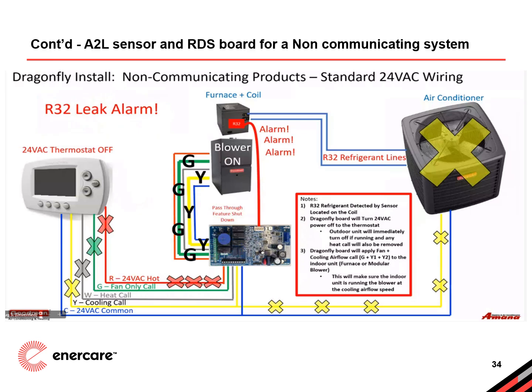At the same time, the RDS controller forces the indoor blower to run at cooling speed. This is a crucial step because it helps ventilate the area and dilute any refrigerant concentration. The benefit to this setup is that the RDS board usually just acts as a pass-through for signals between the thermostat and the system. But when something goes wrong, it overrides everything to prioritize safety, even in a low flammability environment. This is especially important in a non-communicating system, like the one shown in the diagram, where everything relies on standard 24-volt wiring. So, with the RDS in place, not only are you notified of a leak through alarms, but the system also takes proactive steps to prevent any hazardous situations.